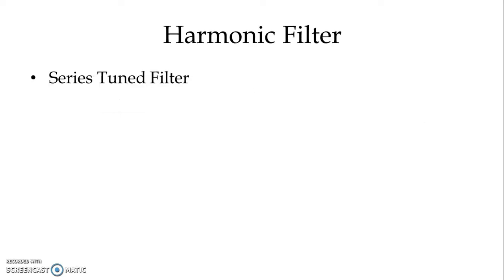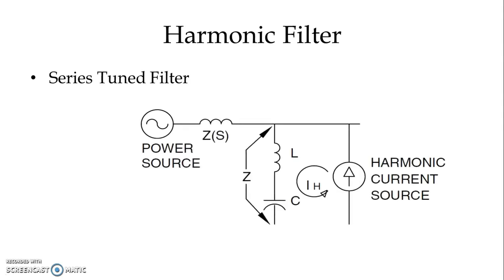First we have the series tuned filter. As shown in the figure, we have a power source and the impedance of the power source. We have a harmonic current source due to a non-linear load, and we have L and C — that is the series tuned filter — which is connected across the harmonic current source.